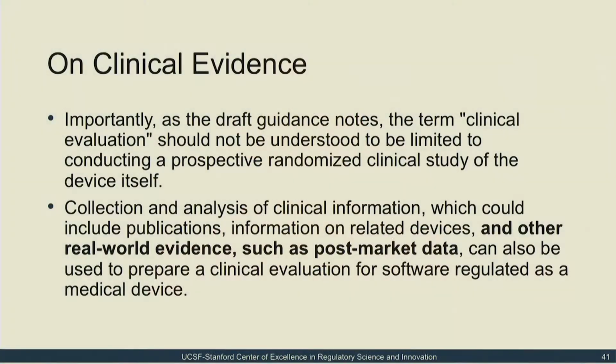Altogether, evidence should allow both the manufacturers and users to determine that the product is appropriate for its intended use, performs as expected, and it is safe. Importantly, the draft guidance does not and could not explain the specific data requirements for each new software product. Such requirements are always based on the specific design of the product and intended use. What the guidance does do is provide a general framework for considering how to approach clinical evaluation given the complexities of medical software.